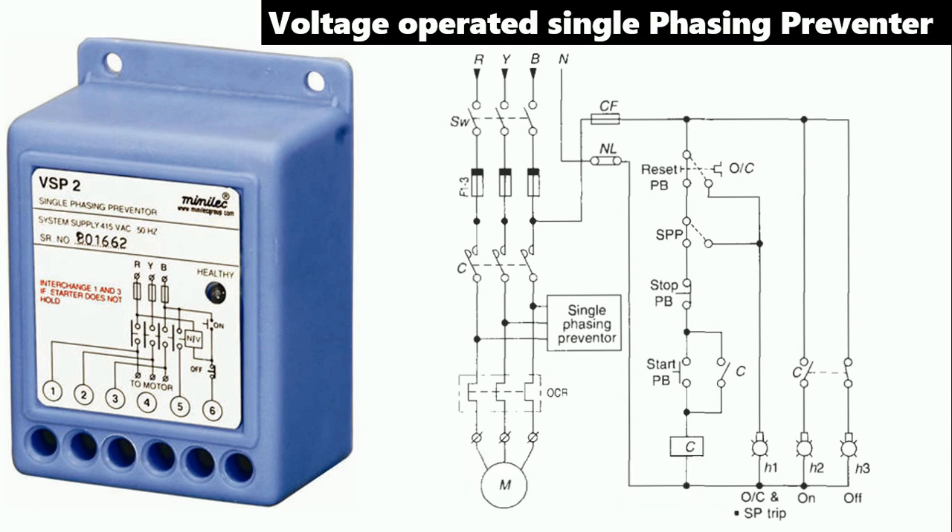The voltage-operated single-phase preventer is mostly used — you must have seen it in your company. If we want to use this for protection of a motor, you can see the circuit diagram here. This is our motor. For protection, an overload relay is used. For turning on and off, a contactor is there. For backup, a fuse is connected. Here, an MCB or main switch is also shown. From here, power supply RYB is given to the motor. To operate the motor, we turn on and off this contactor using a DOL starter.